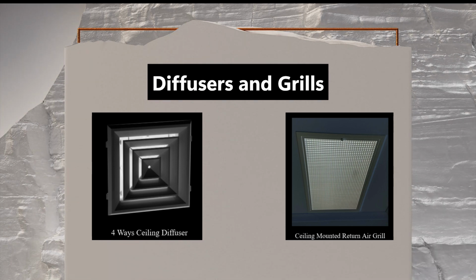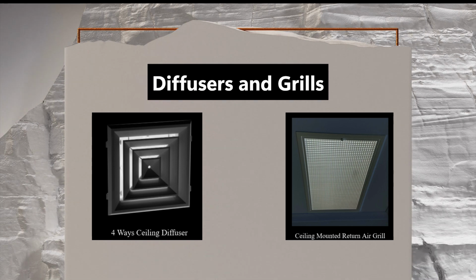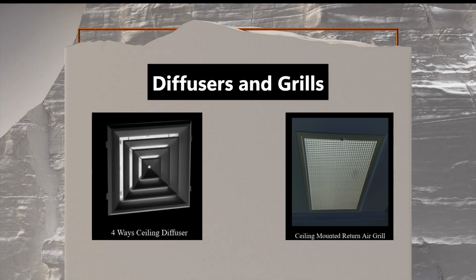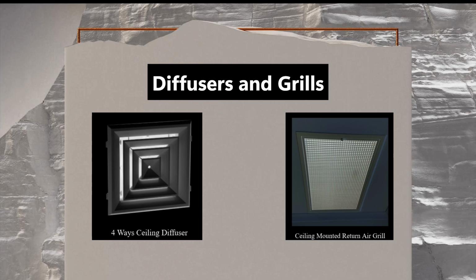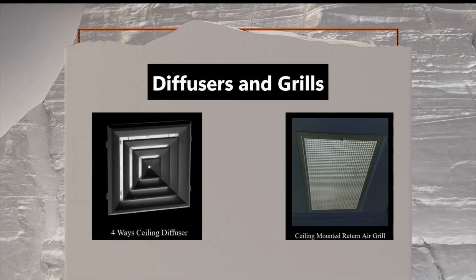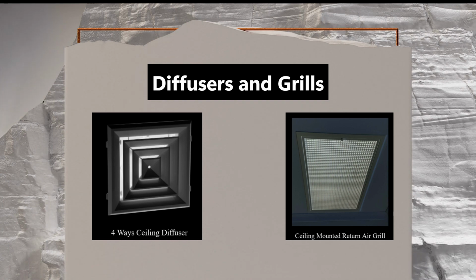To improve energy efficiency and comfort, the system incorporates variable air volume, VAV controls, which adjust the airflow to different zones based on cooling demand. For the startup company space, it is designed that at every branch duct, there will be a VAV box to cater to the different needs of the users, just condition at that space. Therefore, at the 10 startup companies, the volume supplied can be increased or decreased to suit the occupant's desire. The conditioned air is distributed through diffusers, while return grills collect the used air for reprocessing.